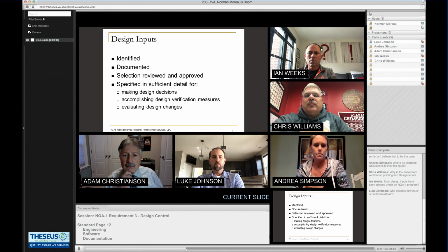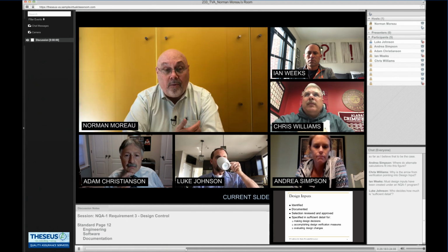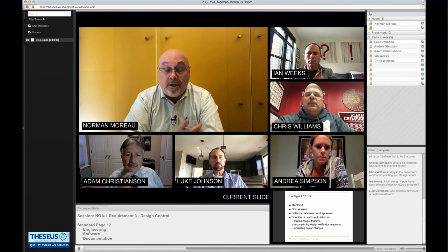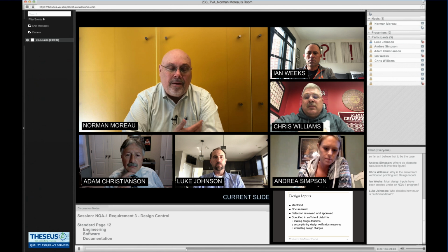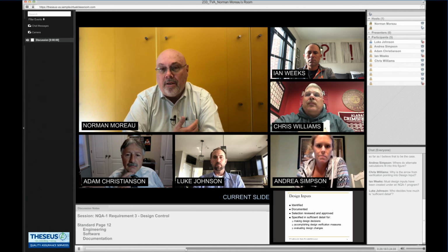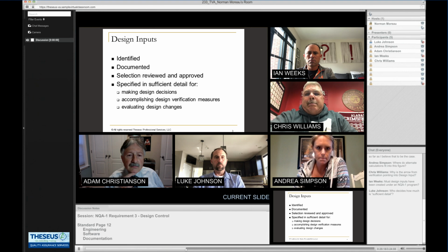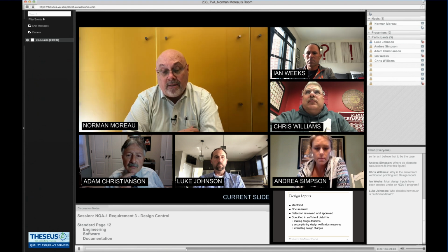The next slide is about design inputs, and there are very specific requirements. Identified, documented. How did we select them? Someone has to review and approve those inputs. Think of things like temperature, humidities, the environment, research papers that are done to support the practice, and then specified in sufficient detail.